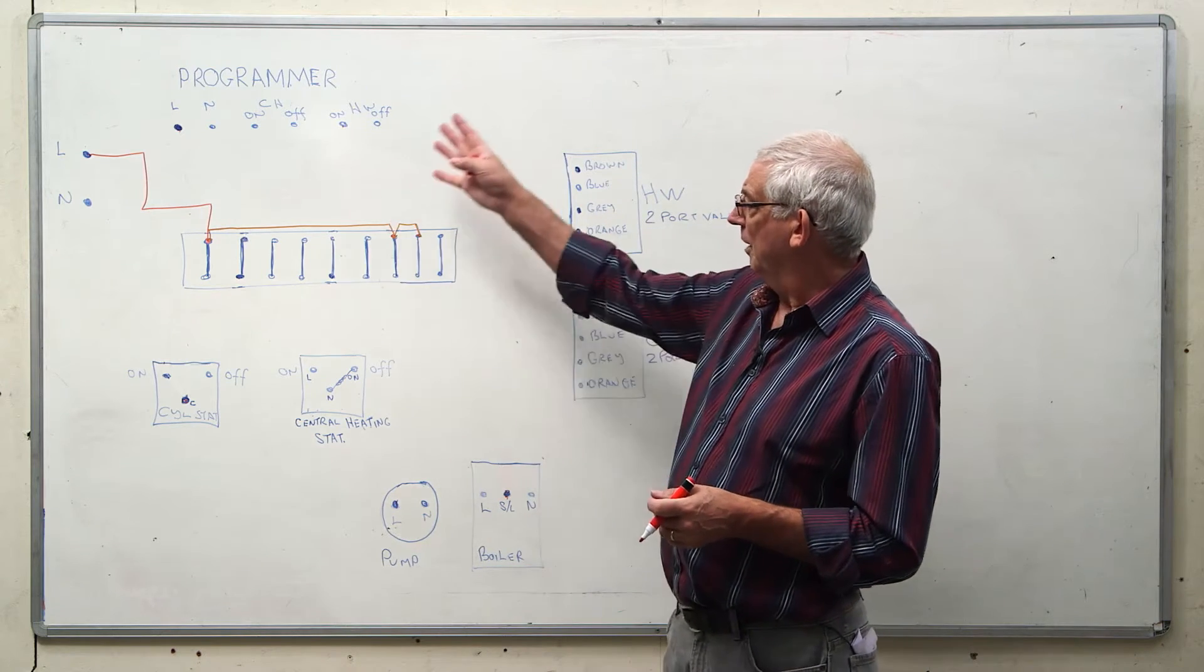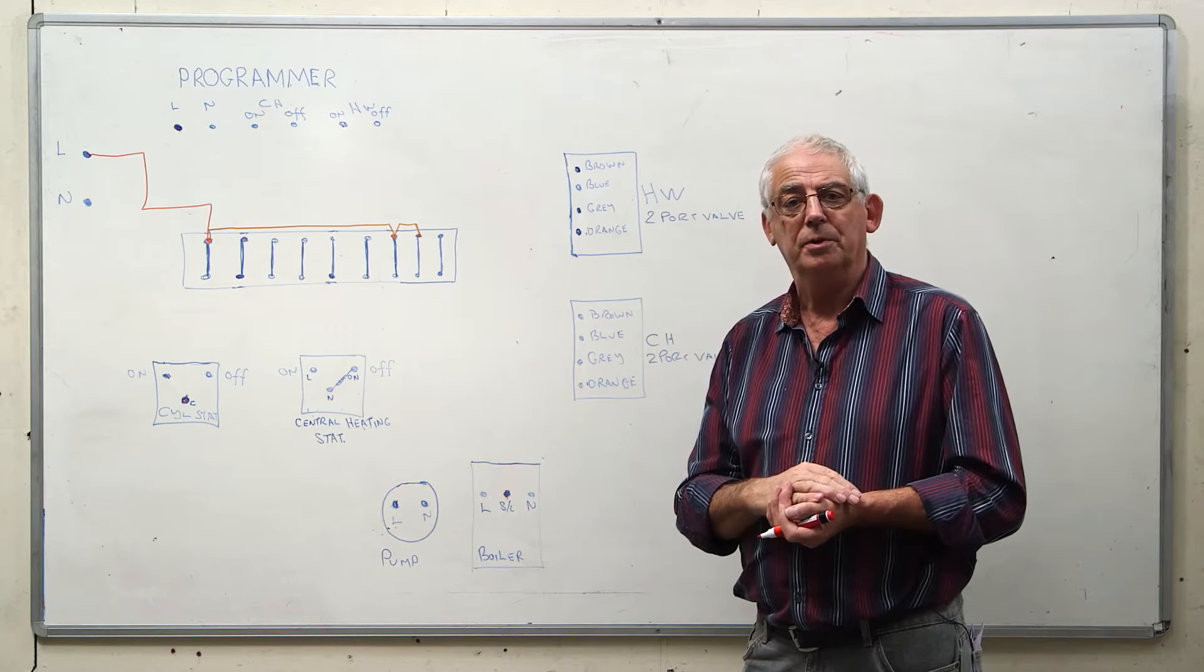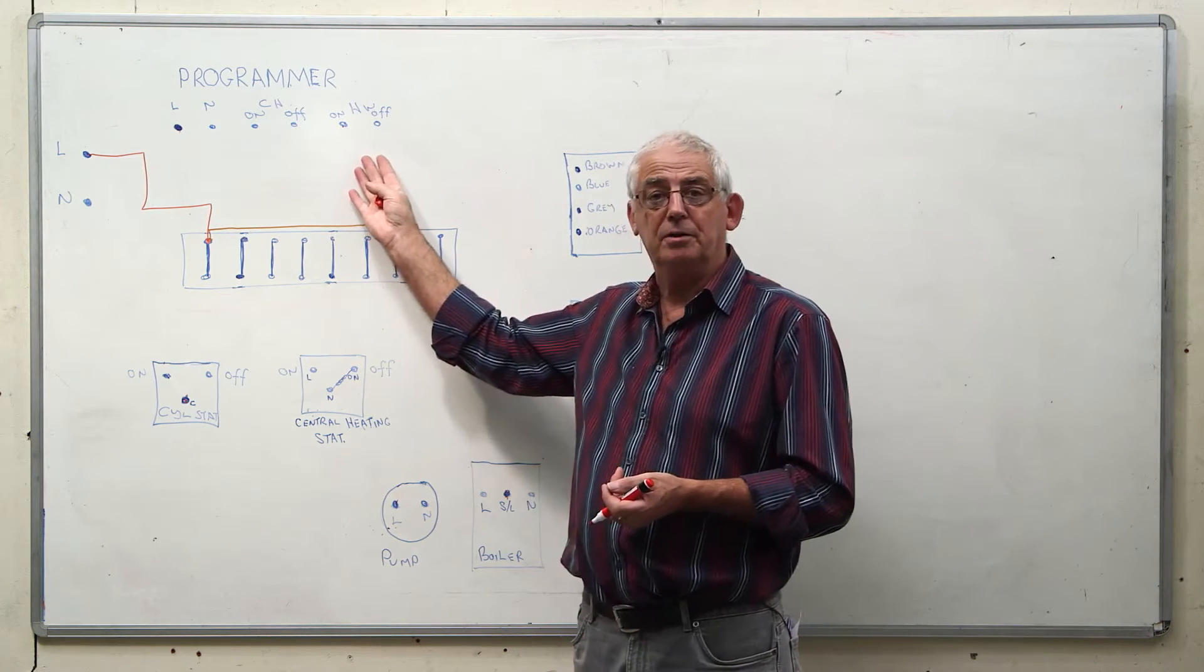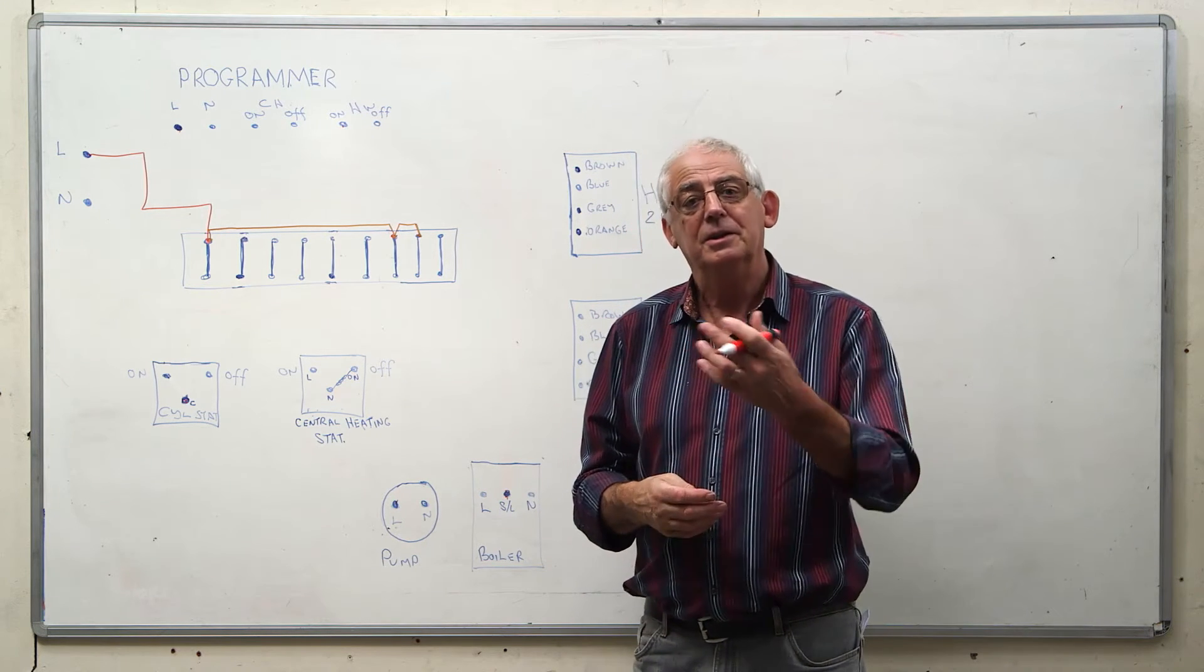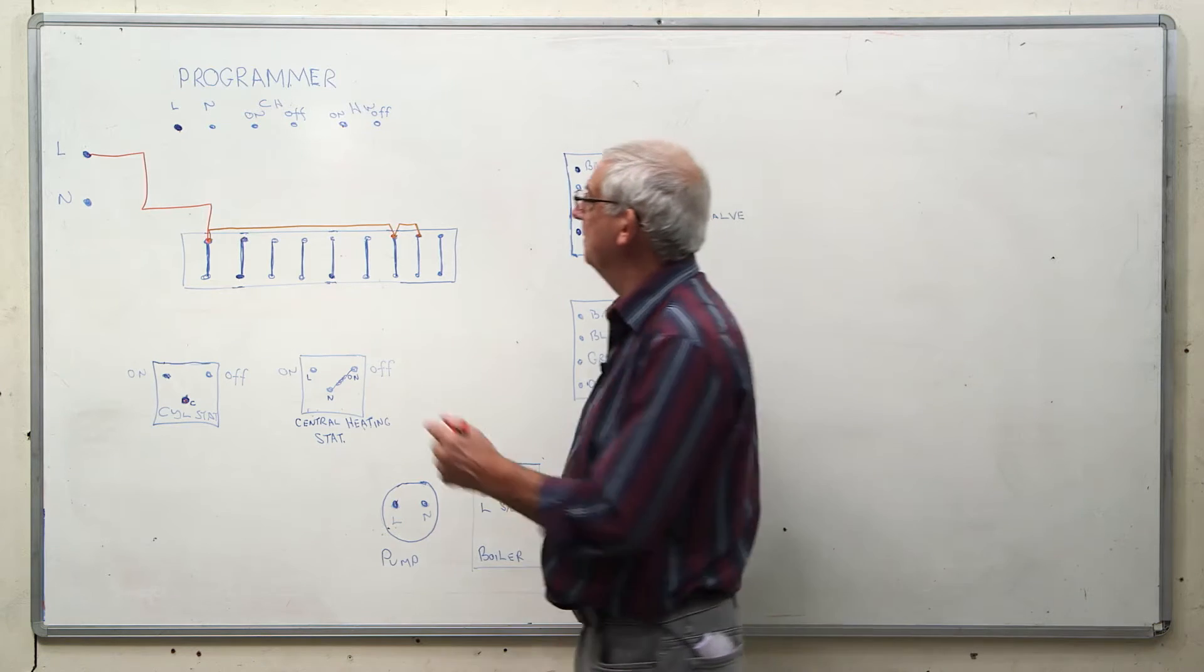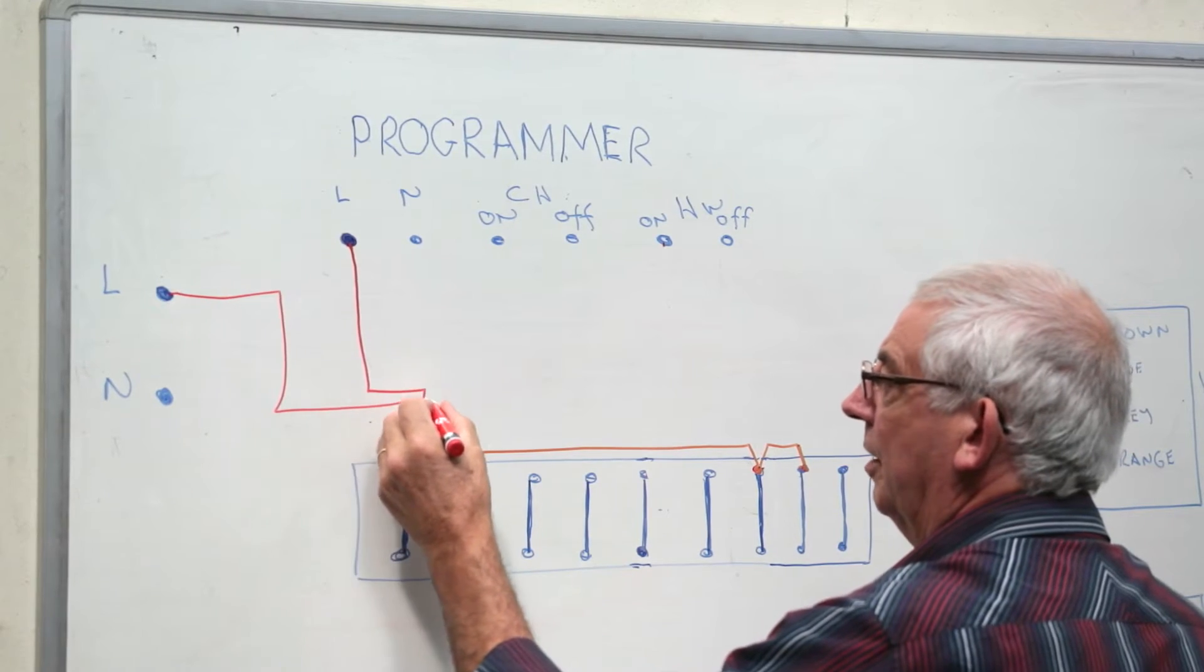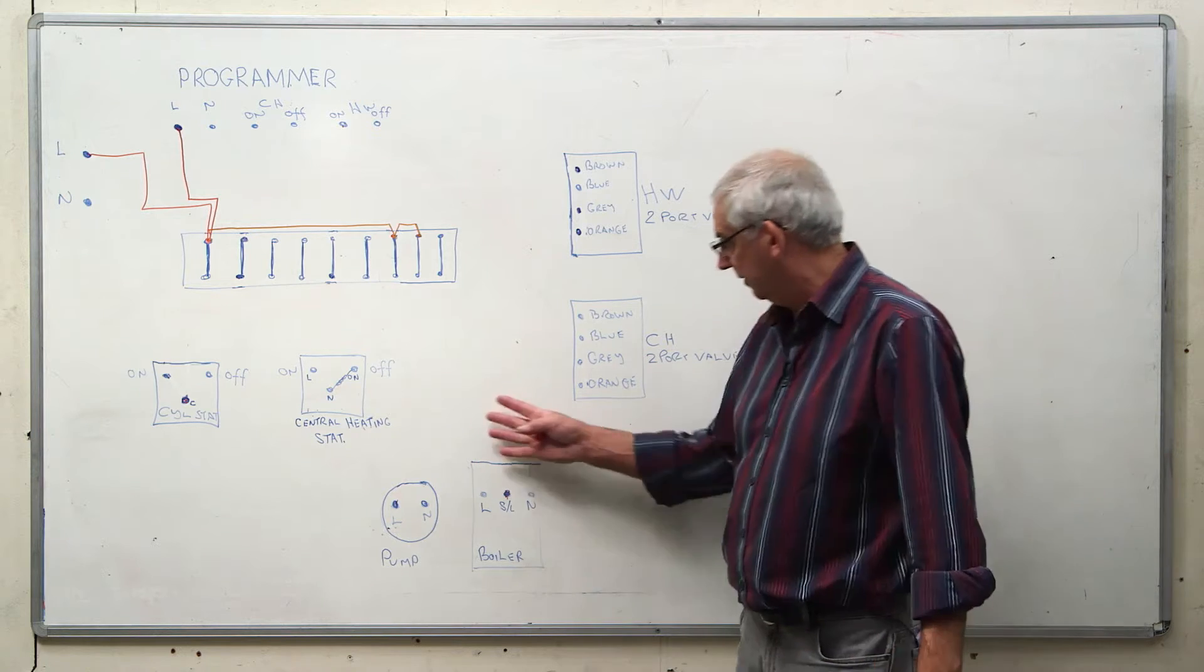I need to look now at the system and see which other parts of that system require a permanent live. Well fairly obviously the programmer does because the programmer is a time clock and the time clock needs power 24 hours a day so I'll run a permanent live to the time clock.